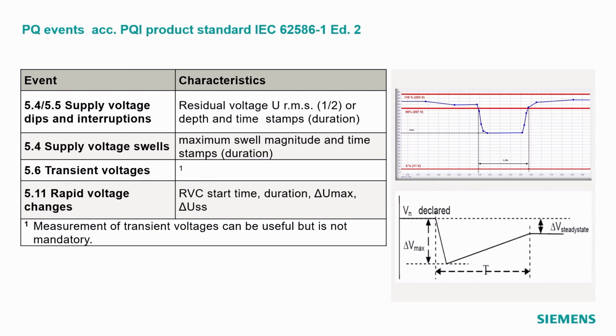voltage event. If the voltage goes out of the plus minus 10% voltage band, then the event starts. And if the voltage is coming back after a while to the 90% border plus 2% hysteresis, then the voltage event ends, and the event is characterized by the start time, by the lowest voltage during the event, and by the end time, so by the lowest voltage or residual voltage or voltage depth and the duration.